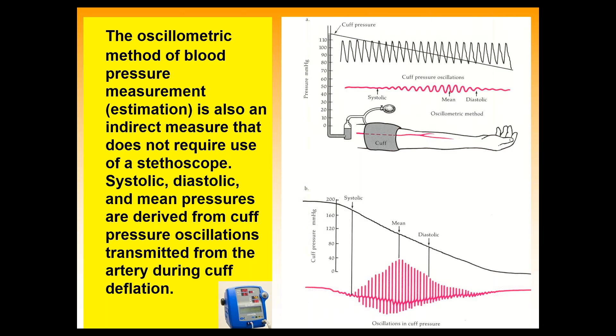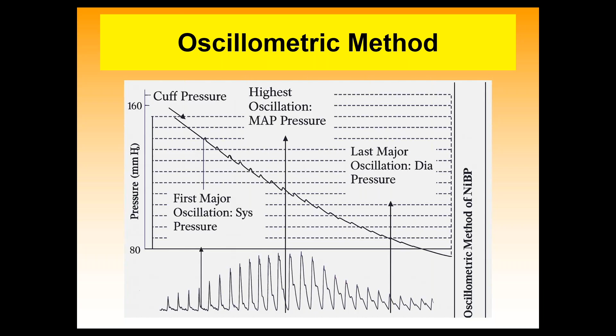Regardless of the machines, because they all have supposedly proprietary algorithms in there, that my systolic is better than your systolic, they got all of that stuff going on. Regardless of the machine, the mean is always at the maximum of those pressure fluctuations. So this is what you kind of get. And of course, these can be set up to take pressures periodically as well. So it's still an indirect method, still giving us an estimate, but it reduces some of the variability associated with stethoscopes.